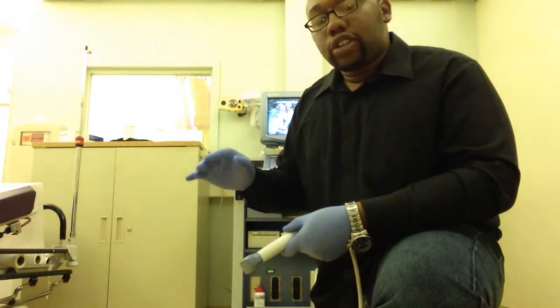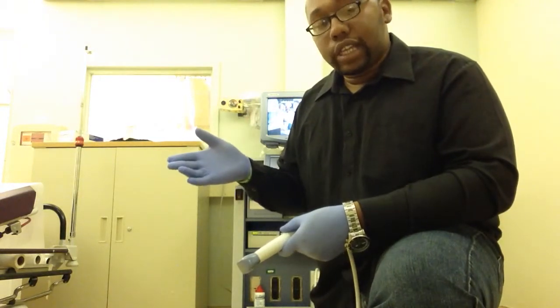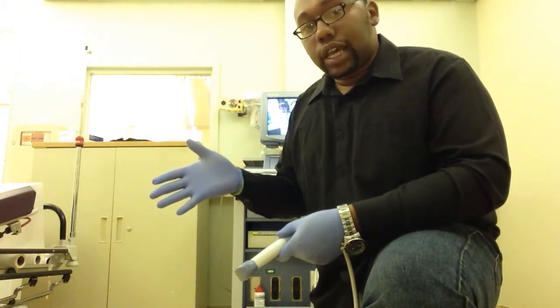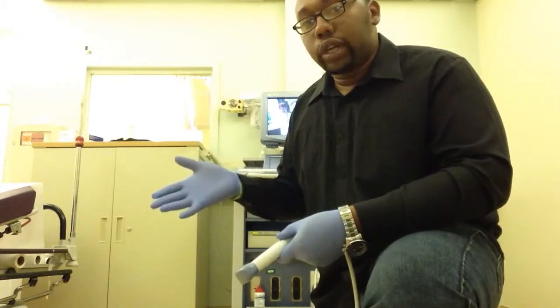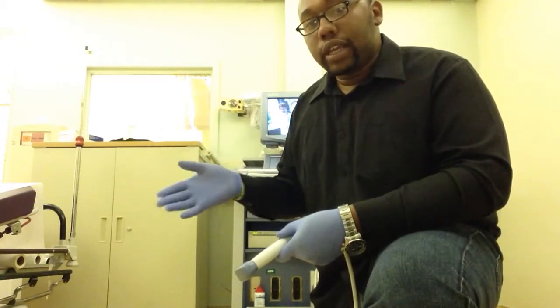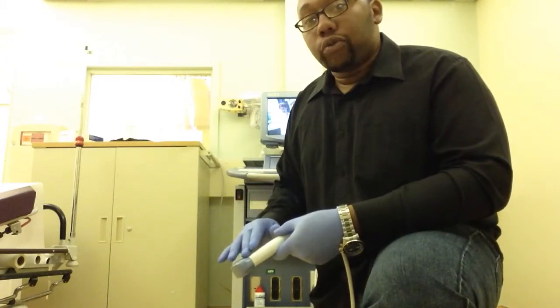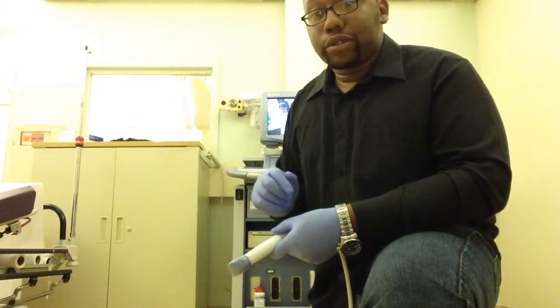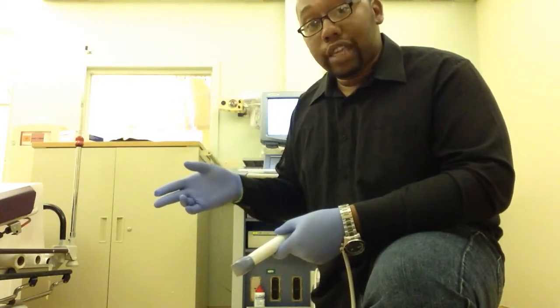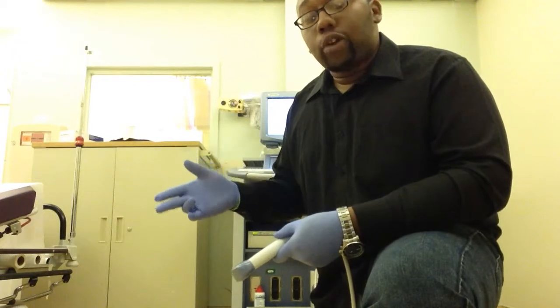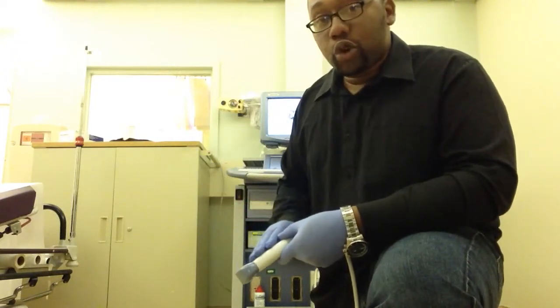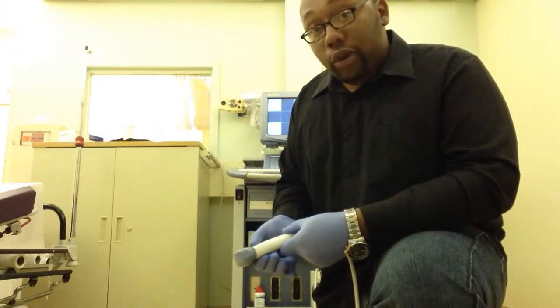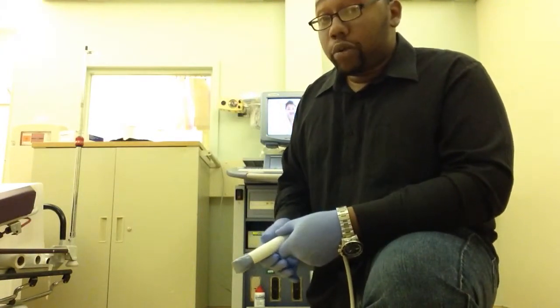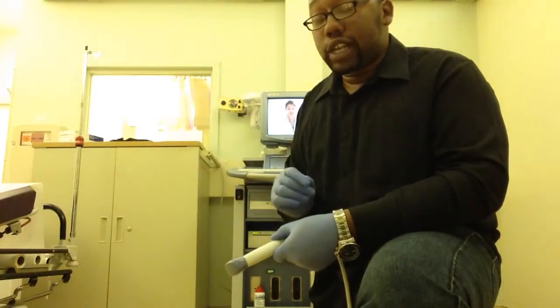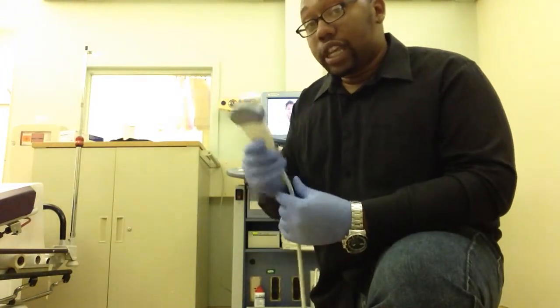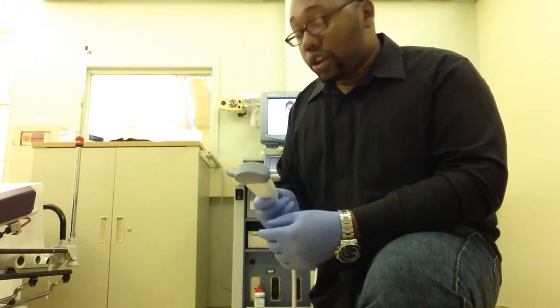All of that data that goes across the hydrophone will be fed into a computer system connected to the hydrophone, with software designed to read the voltage level and make sure we're getting the right amount of return energy, I guess you would say, that sound energy being converted back into electrical energy. That will show us that our transducer's working right. Okay? If we don't get the right readouts, then we know that our transducers are not working right. Basically, that's the calibration for the ultrasound machine as a whole. We basically just test each one of these transducers to make sure that they're working right.